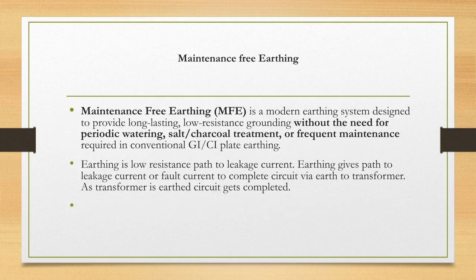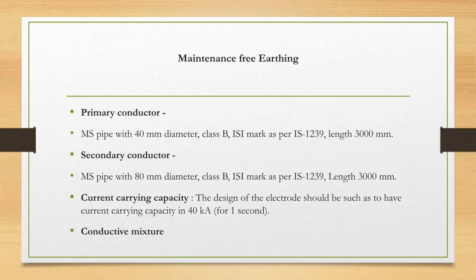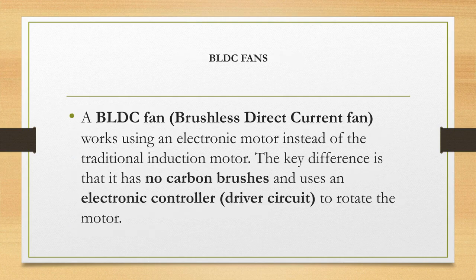Maintenance-free earthing, or MFE, provides long-lasting, low-resistance grounding without the frequent maintenance of conventional systems. Earthing ensures a low-resistance path for leakage or fault current to complete the circuit via earth to the transformer. The MFE system uses primary and secondary MS pipes as conductors, each 3,000 millimeters in length, and a conductive mixture. The electrode is designed to have a current carrying capacity of 40 kiloamperes for 1 second.